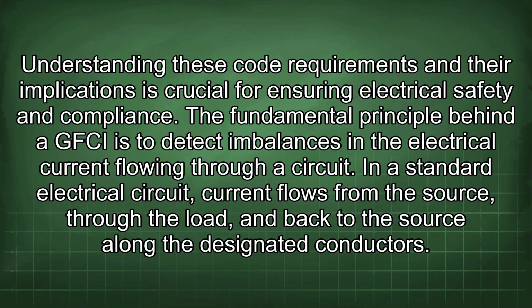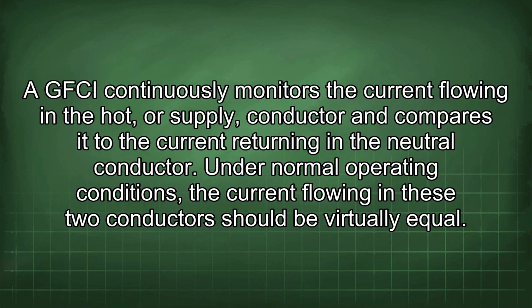The fundamental principle behind a GFCI is to detect imbalances in the electrical current flowing through a circuit. In a standard electrical circuit, current flows from the source through the load and back to the source along the designated conductors. A GFCI continuously monitors the current flowing in the hot or supply conductor and compares it to the current returning in the neutral conductor. Under normal operating conditions, the current flowing in these two conductors should be virtually equal.